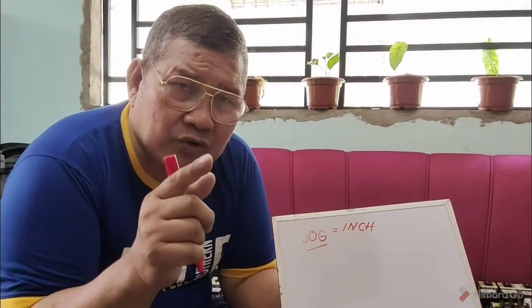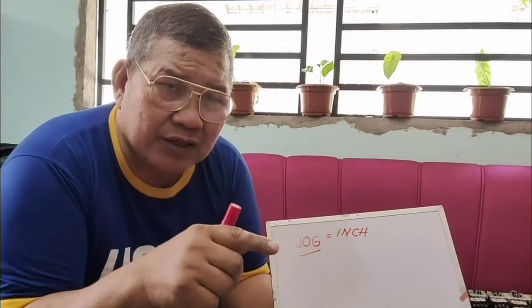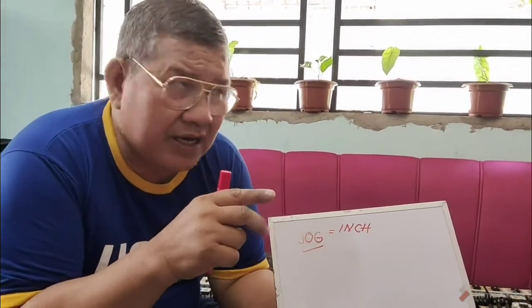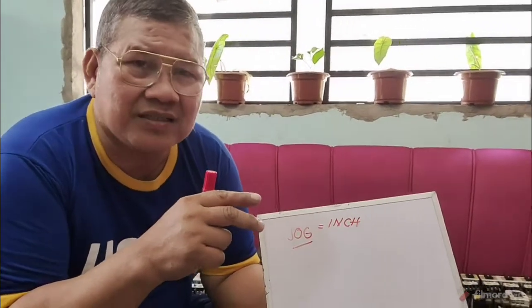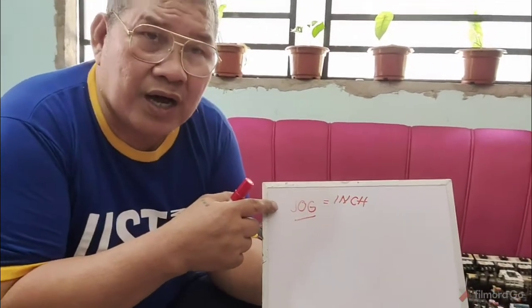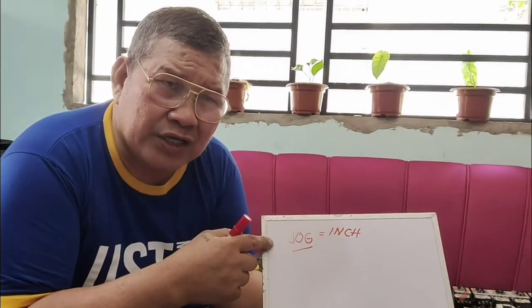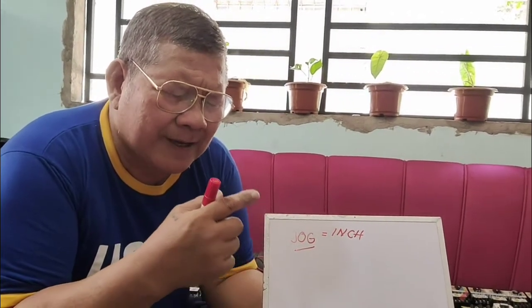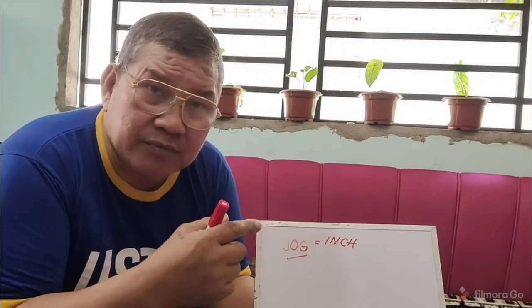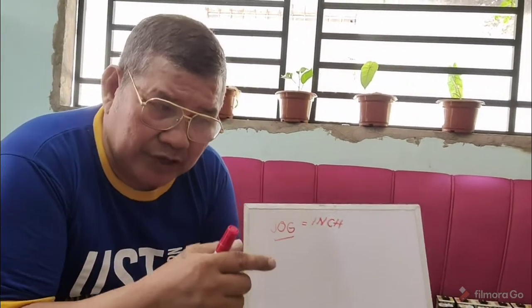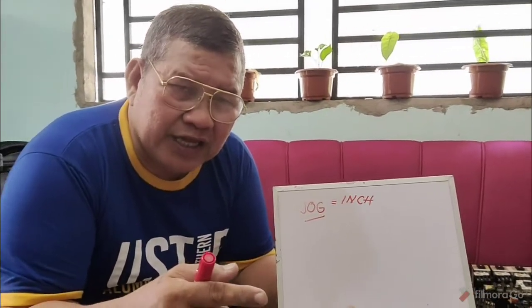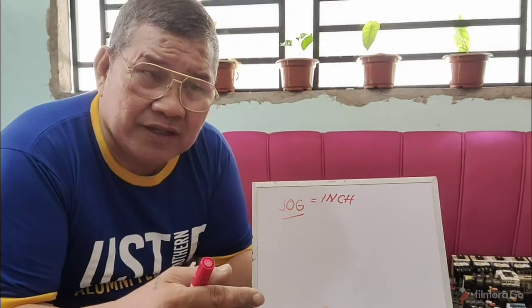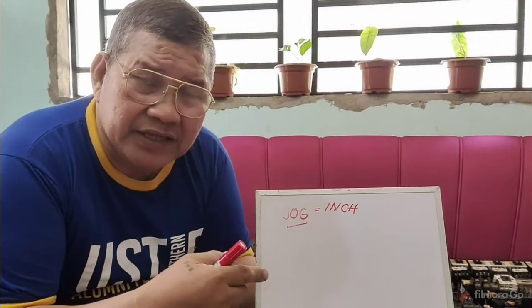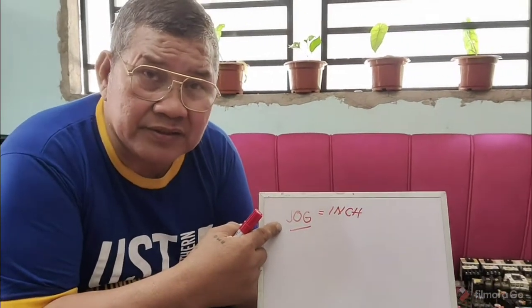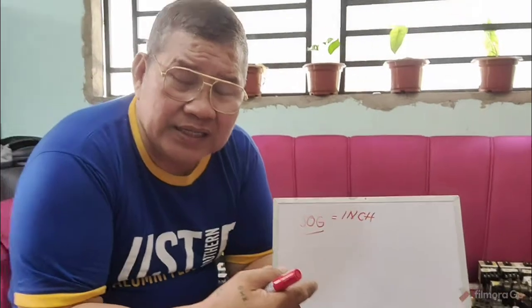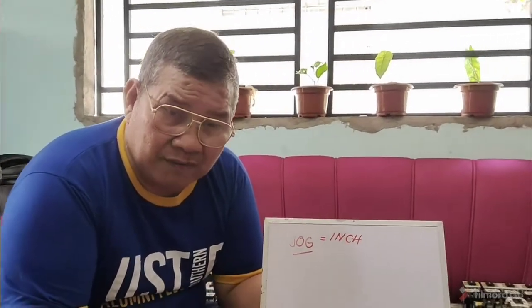But if you want to run the motor for a short period of time, maybe to test the alignment or the distance, you need the jog button. It's usually installed in machines like a lathe, in a machine shop. If they have a piece being set up in a lathe machine and want to check if it is already aligned, instead of pressing the start button, they press the jog button first. Once it's aligned, they press the start button to begin the operation.